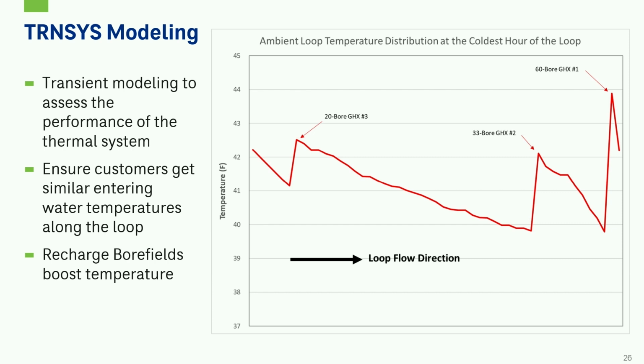And so you can see as each customer is connected, we get slowly lower and lower temperatures from about 42.5 down to just below 40 degrees, where we have a recharge bore field where we're able to take heat from the ground to boost our entering water temperature. And then the process repeats with the customers along that next line.